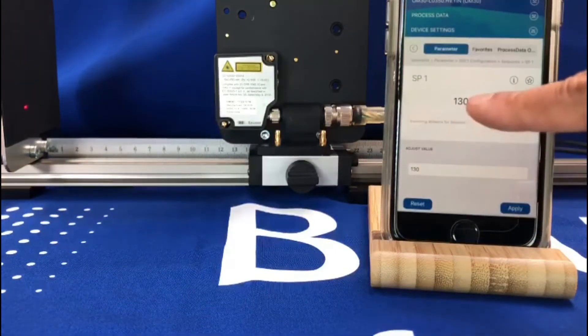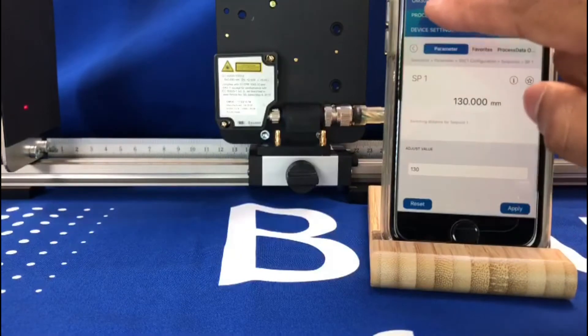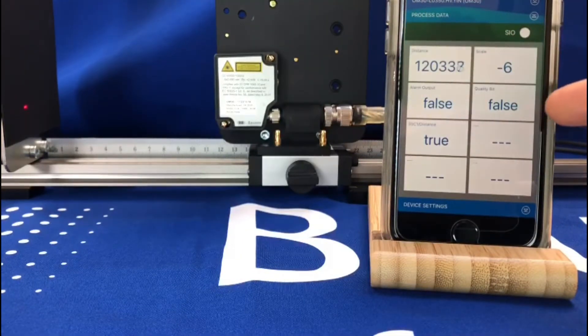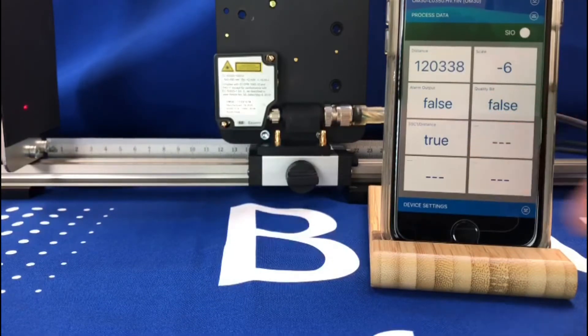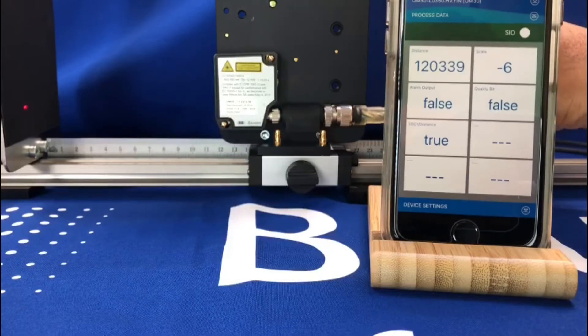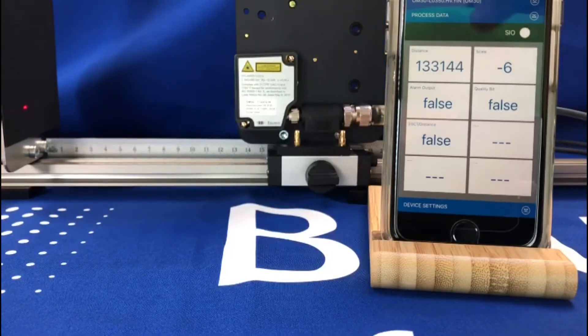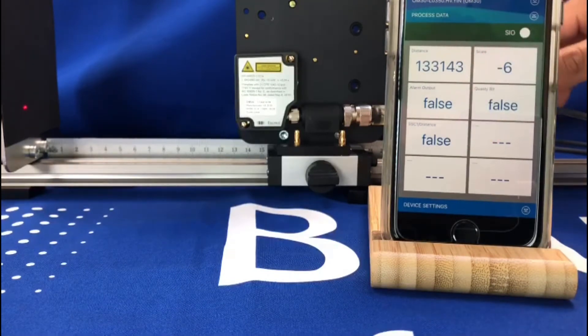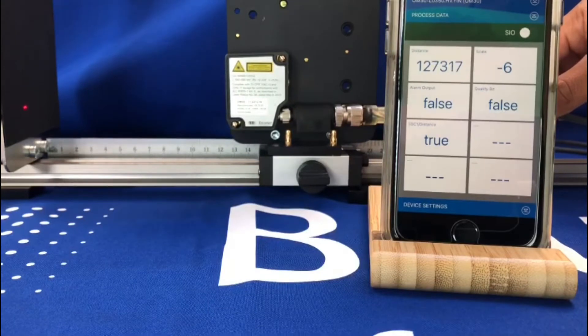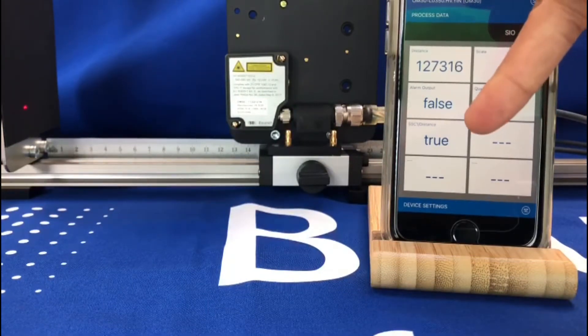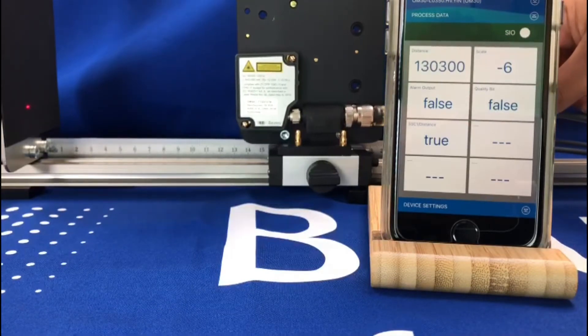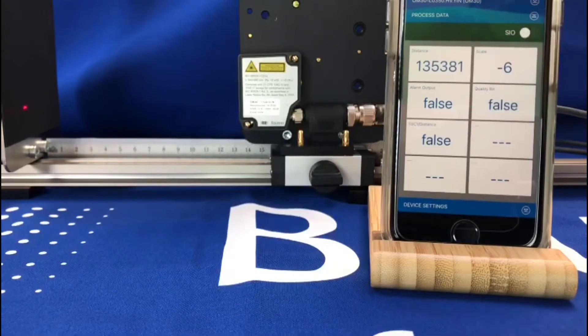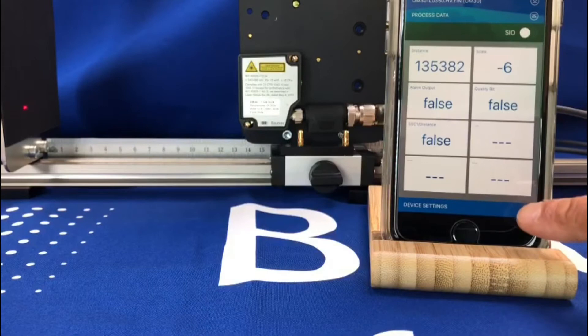If I go back now and set a distance, SSC1 configuration set a set point, let's say 130 mil something like that, seeing as we set up at 120 mil. Apply, so now that's set. If I go to process data, you can see the output is currently on at 120 mil. If I now move the sensor back over 130 mil, you see the output goes off. And of course you can switch the polarity. Move it closer, over inside 130 mil the output switches to true. Outside of 130 mil the output switches to false.